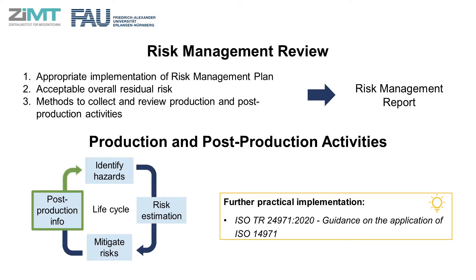This concludes the initial implementation of a risk management plan. Now the manufacturer shall review whether: 1. the risk management plan has been appropriately implemented; 2. the overall residual risk is acceptable; and 3. appropriate methods are in place to collect and review information in the production and post-production phases. The review results are documented in a risk management report at the conclusion of the current risk management.